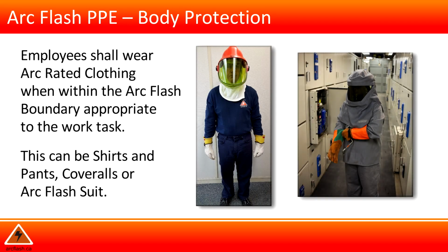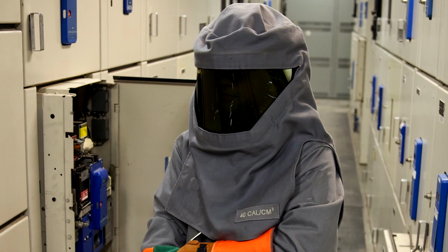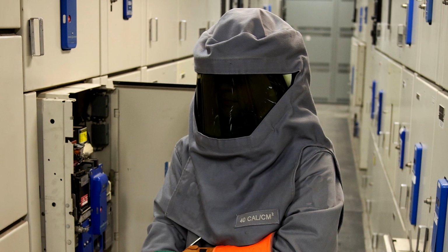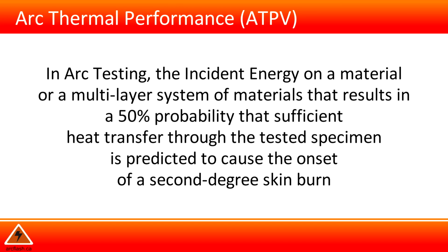Employees shall wear arc-rated clothing when working within the arc flash boundary, appropriate to the calculated incident energy or the work task. This can be shirt and pants, coveralls, or the arc flash suit. The entire arc flash suit, including the hood's face shield, shall have an arc rating that is suitable for the arc flash exposure. The arc thermal performance value, or ATPV, in arc flash testing, is the incident energy on a material or a multi-layer system of materials that results in a 50% probability that sufficient heat transfer through the tested specimen is predicted to cause the onset of a second-degree skin burn.